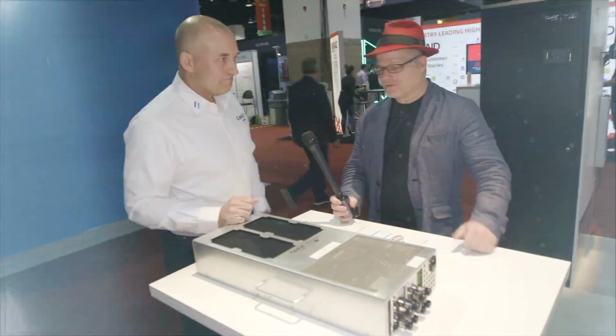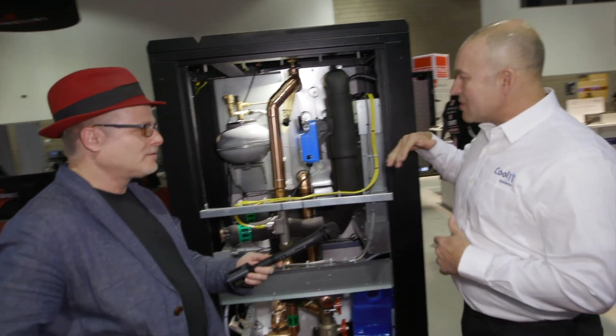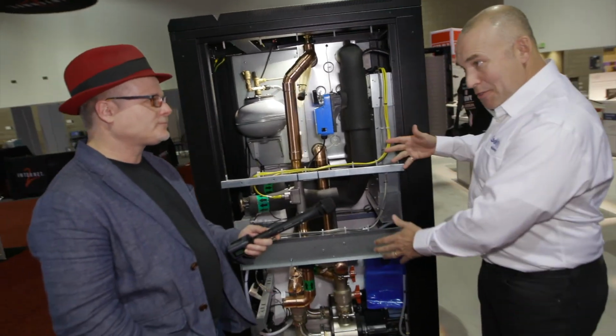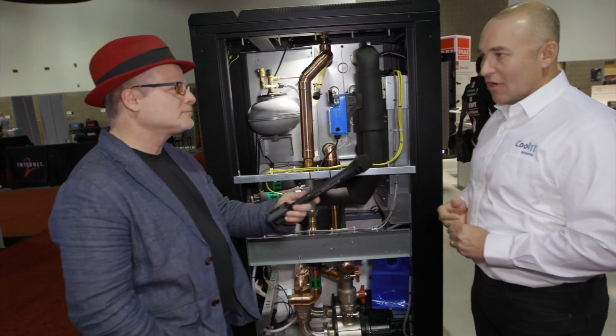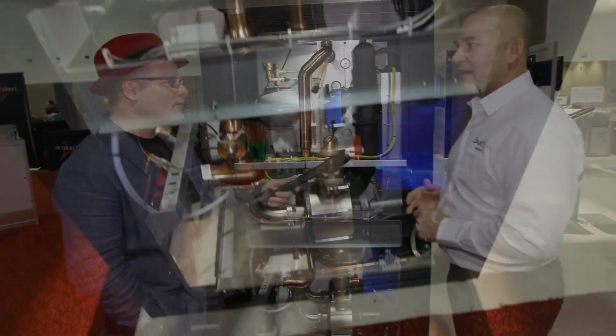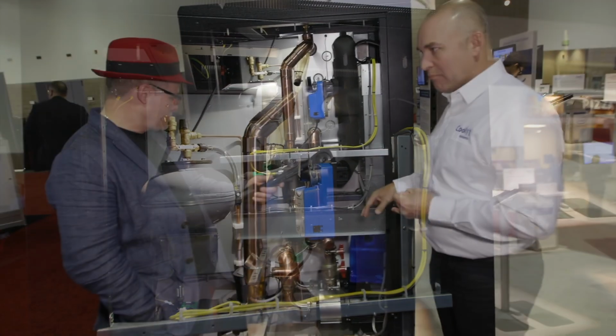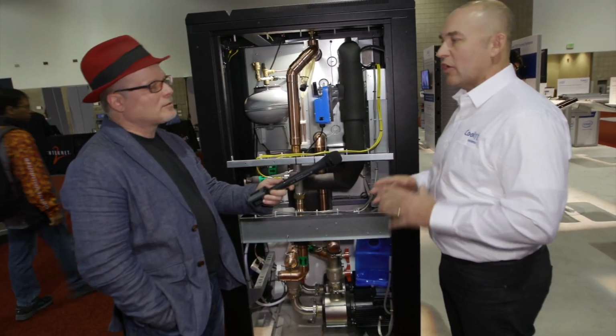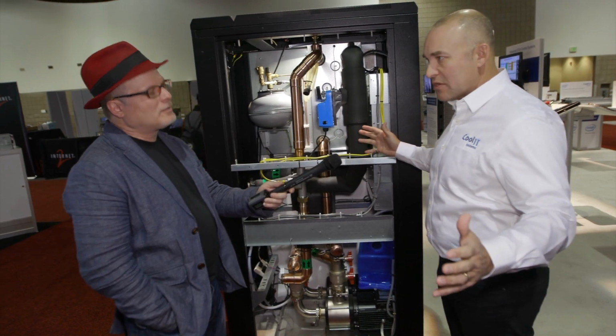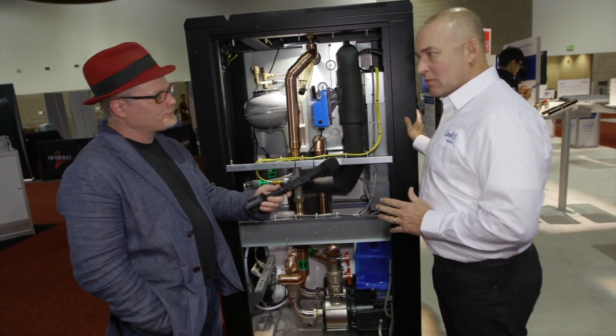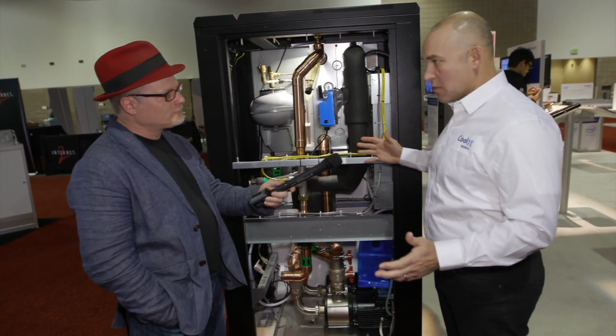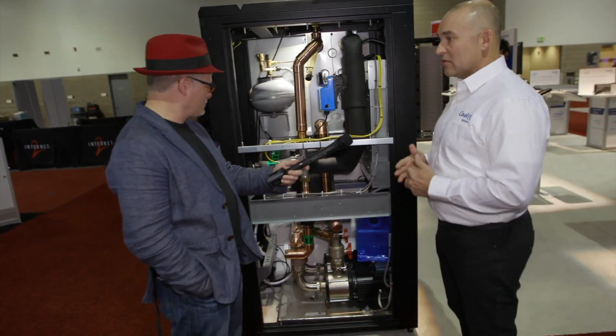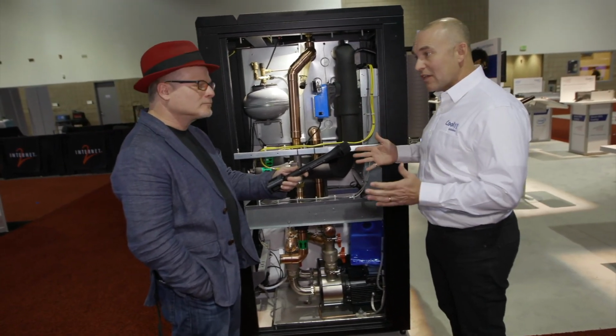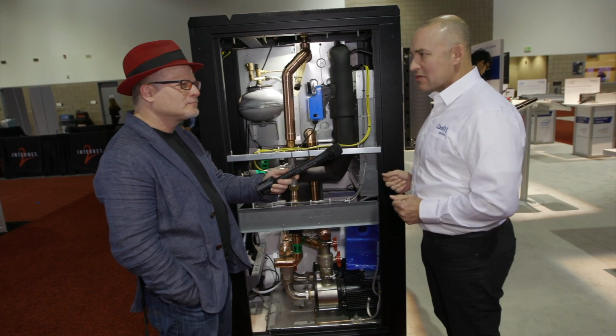Okay, cool. Yeah, so this, you know, the opposite end of the scale. This is our large row-based cooling unit. It's a CDU, and this supplies centralized pumping support for our coolant to go to all of the rack manifolds. This becomes a practical option when you have more than, say, 5 or 6 racks. This could handle up to, well, depending on the density of each rack, about 700 nodes.